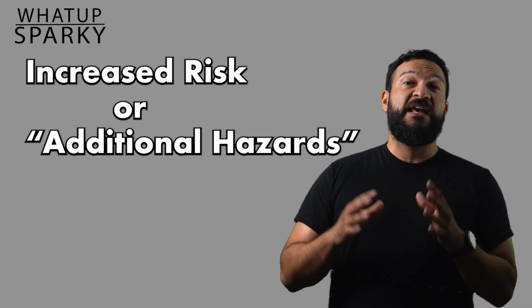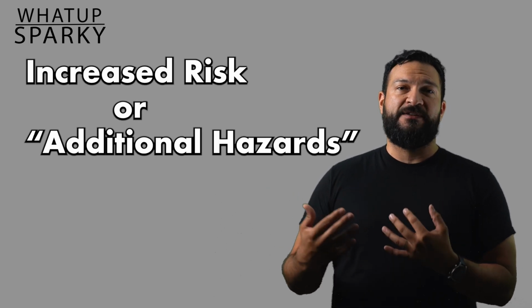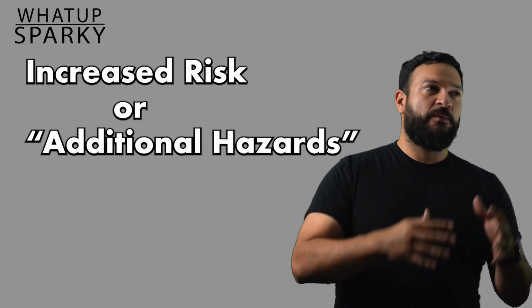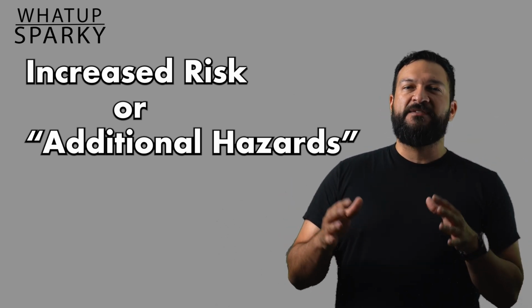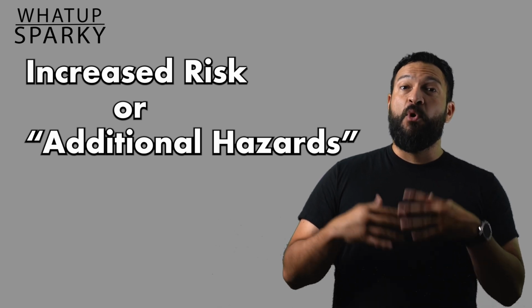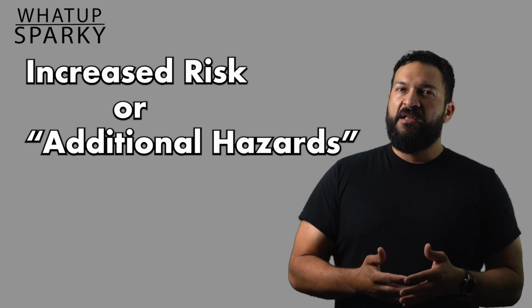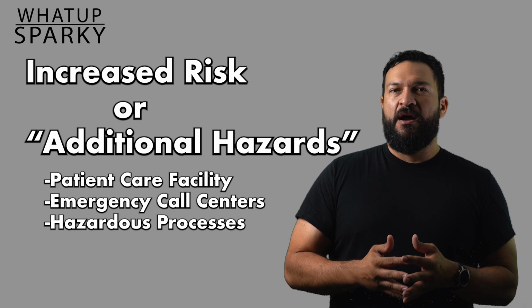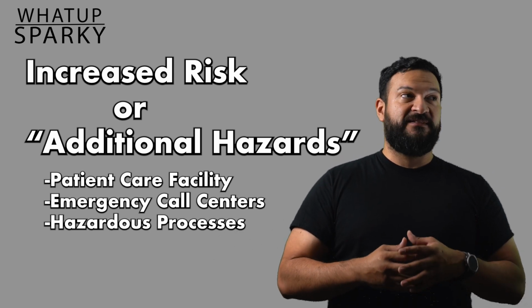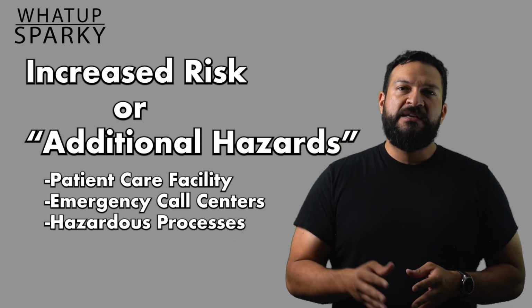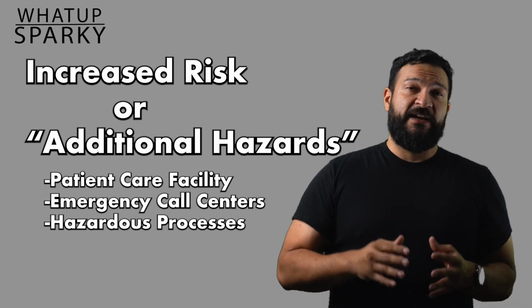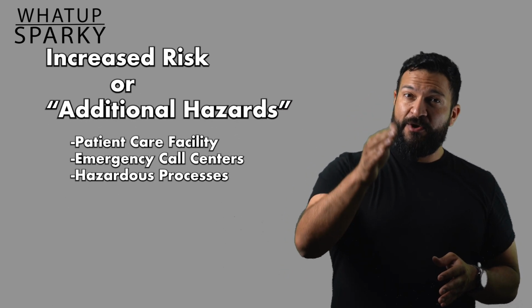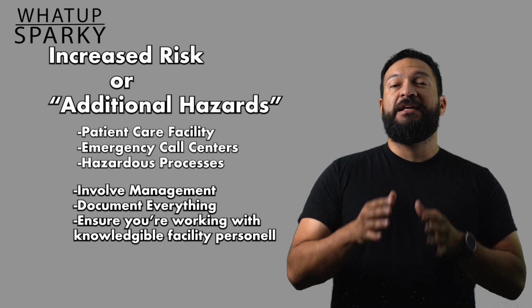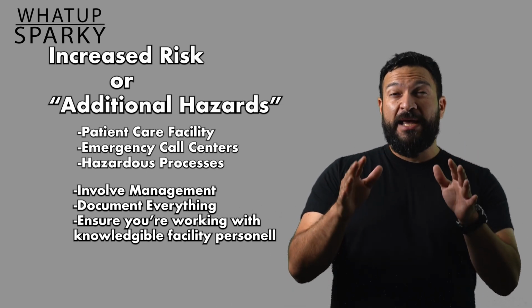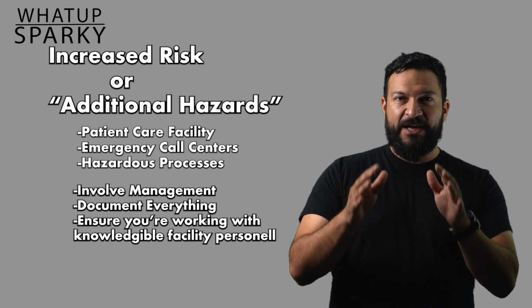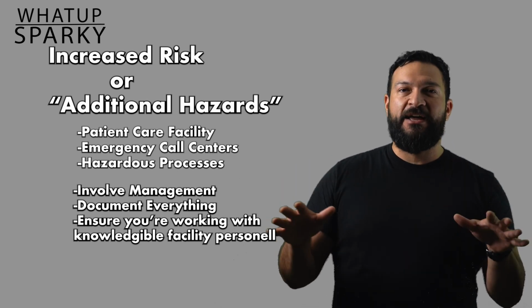And the last one is increased risk or a greater hazard. Now this one shows up in hospitals, 911 centers, critical factories, or places where shutting down the power might create more of a risk than doing it energized. Like it could jeopardize patient care, emergency response, or even like release a toxic gas in a factory or something. So energized work can be justified in that case, but not by you alone. You need to involve management, you need to document the risk assessment, and plan the work with the right people, the ones that actually know what you're doing and what really matters in the facility.